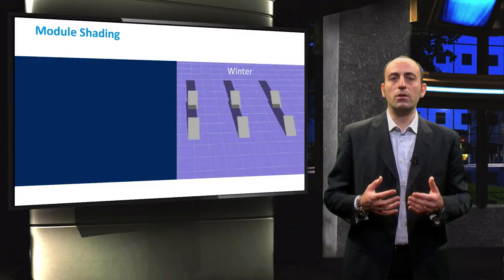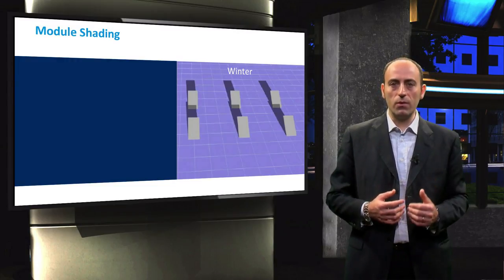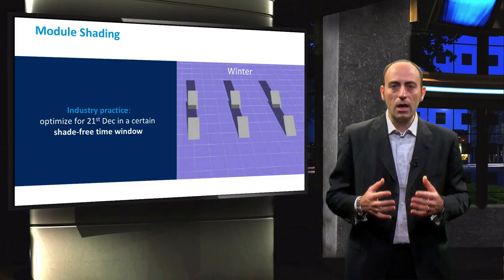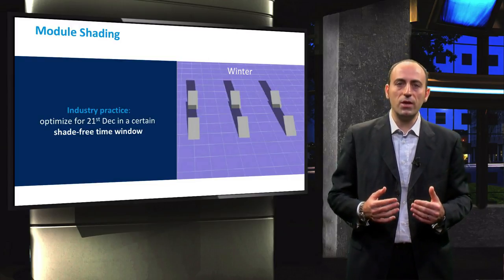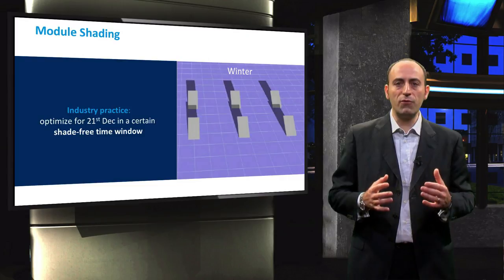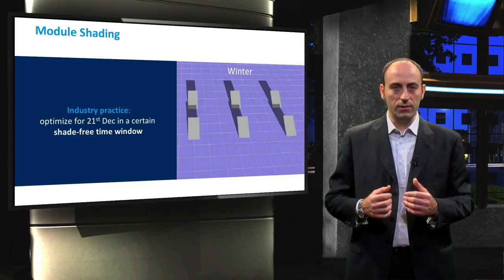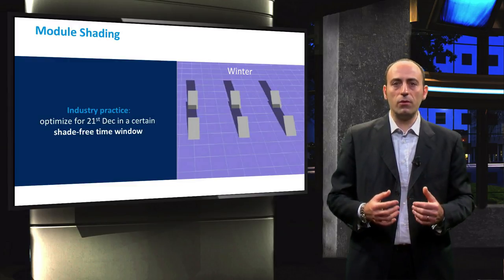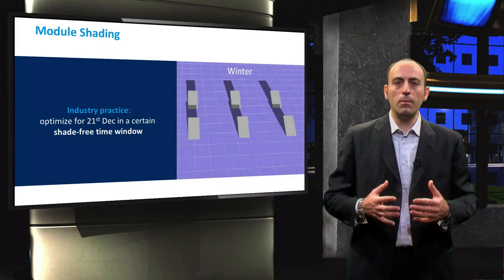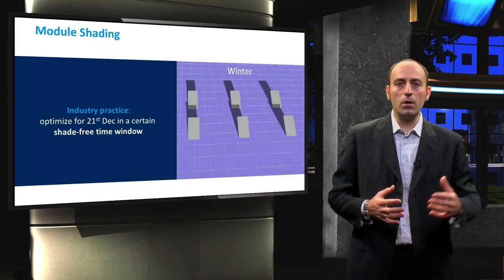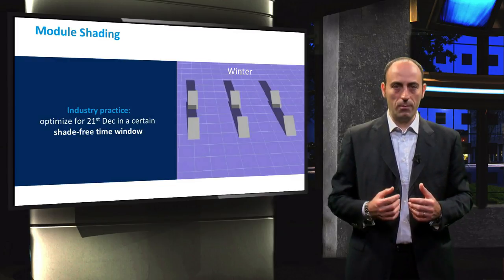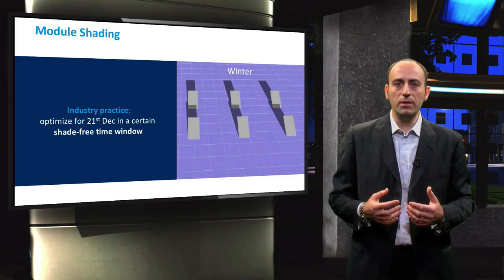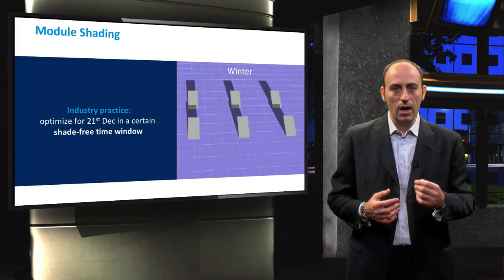Since the length of the shadow is the longest when the sun is lowest on the horizon, reaching its minimum on the 21st of December, it is common practice for installation companies to design and optimize the PV system for a shade-free time window on this date. Normally, this shade-free interval of time is an input from the customer, which needs, for example, the maximum power achievable by the system from 10 am to 2 pm. Then, based on this input, the engineer calculates what should be the inter-row spacing. Let's see how to do it.